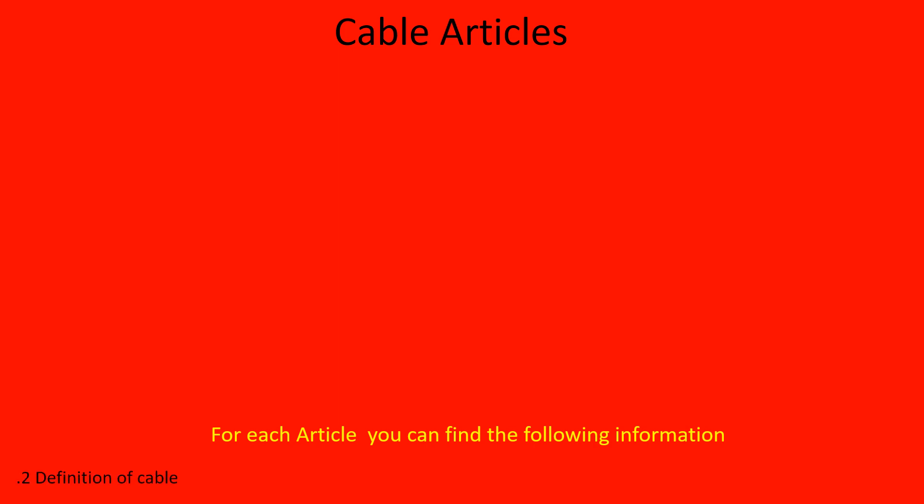In each one of these articles, you could have a dot-two section — that's going to be the definition of the cable. If you're wondering what any one of these cables are, you can go to that dot-two section and it will tell you the general definition. You could have a dot-ten section, which is the uses permitted — where am I allowed to use this cable? Also, dot-twelve is the uses not permitted — where and in what manner am I not allowed to use this cable?